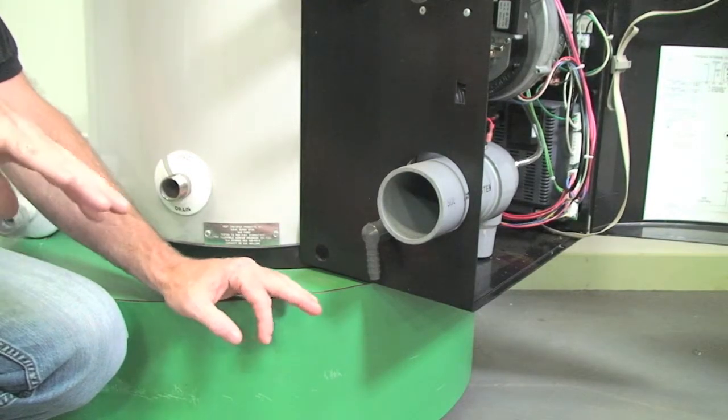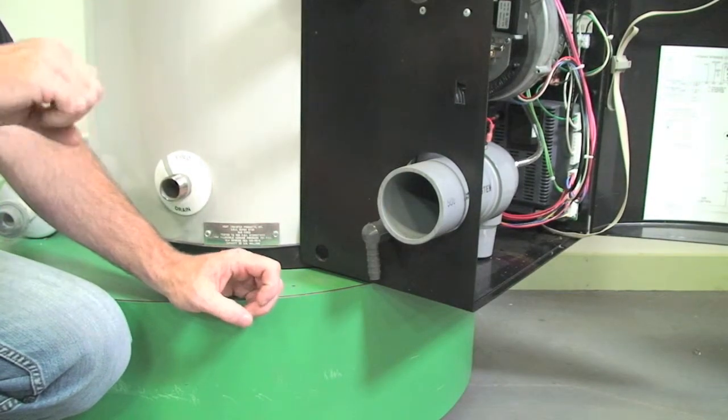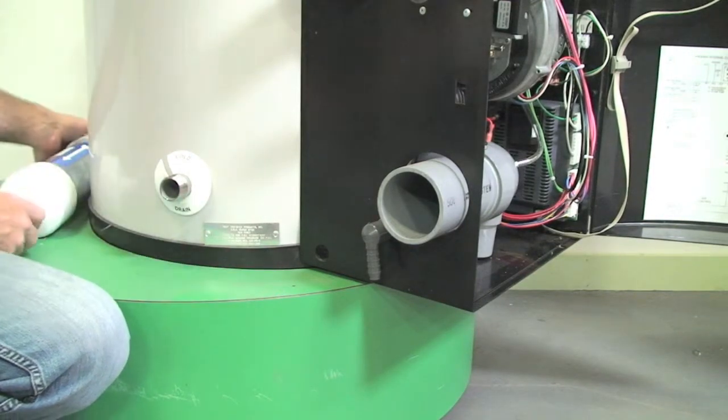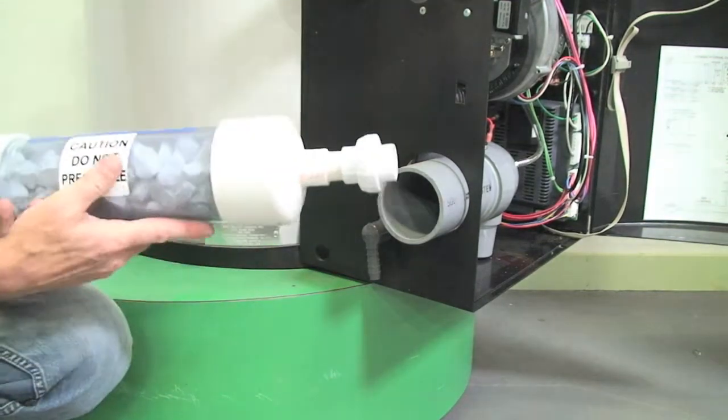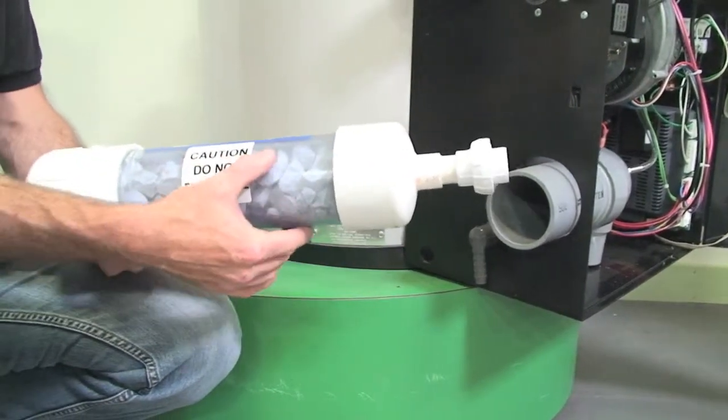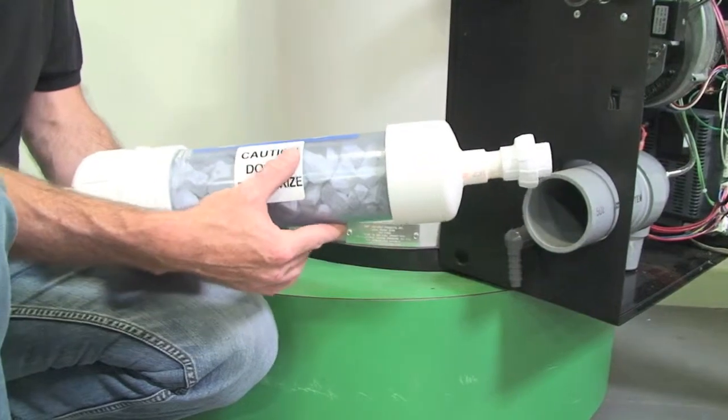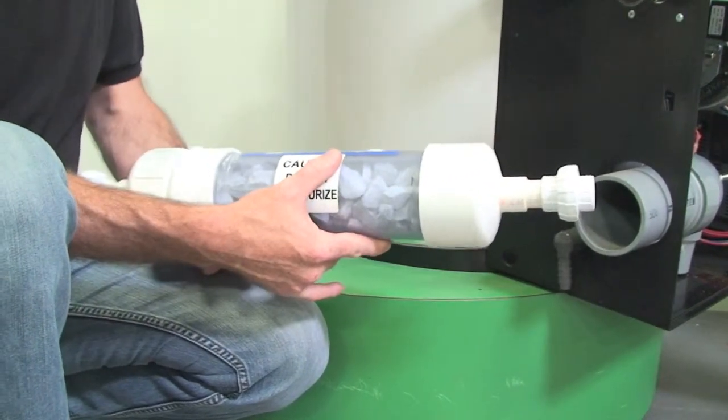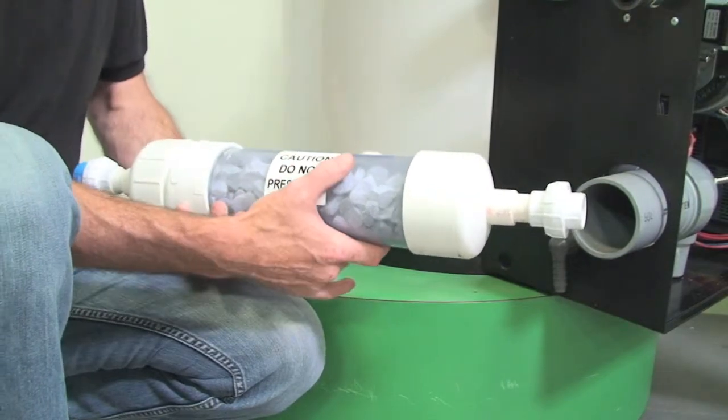Again, as we mentioned, condensate from the combustion process is acidic. In order to neutralize it to dump it into some drains, it may be required to add a condensate neutralizer, which I have here. These are simply marble chips that, as the condensate goes through here, will erode. It is rechargeable. During our annual maintenance, we will take a look at this, make sure it's still filled with marble chips, and replace if necessary.